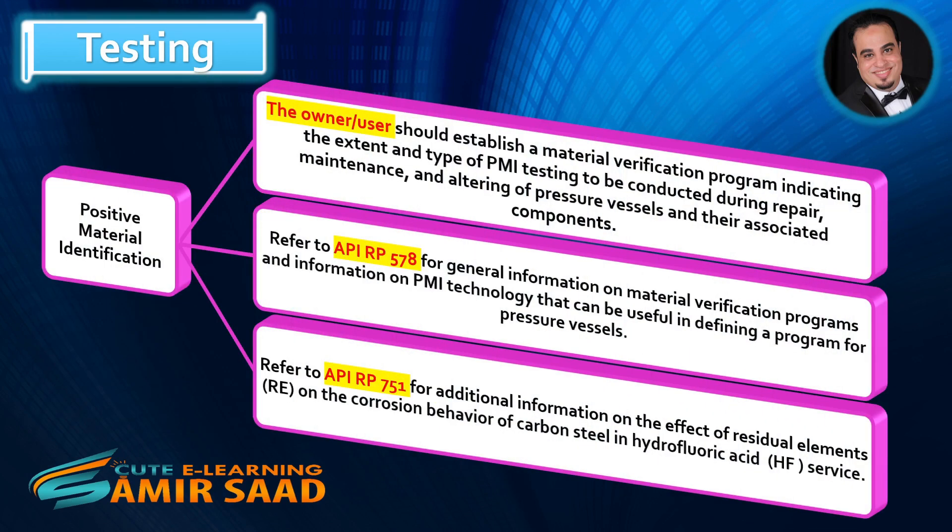Positive Material Identification. The owner-user should establish a material verification program indicating the extent and type of PMI testing to be conducted during repair, maintenance, and altering of pressure vessels and their associated components. Refer to API RP 578 for general information on material verification programs and PMI technology. Refer to API RP 751 for additional information on the effect of residual elements (RE) on the corrosion behavior of carbon steel in hydrofluoric acid (HF) service.